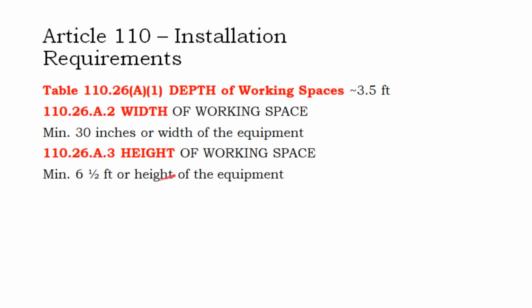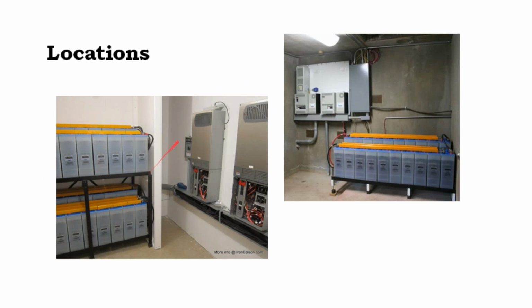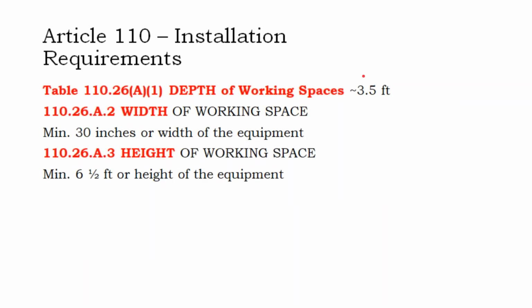There's a few issues. For one, you need working space along the batteries, and it depends on whether you're up against a wall or other electrical devices what that working space is, but generally it's about 3.5 feet. The width of the working space is actually the easiest one—it's a minimum of 30 inches or the width of the equipment, so normally you don't have to worry about that. The height of the space is 6.5 feet, or the height of the equipment, whichever is greater.